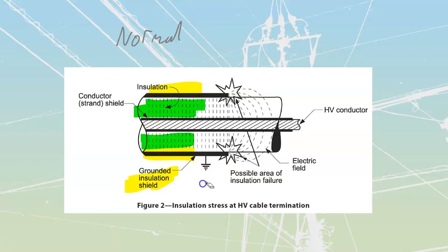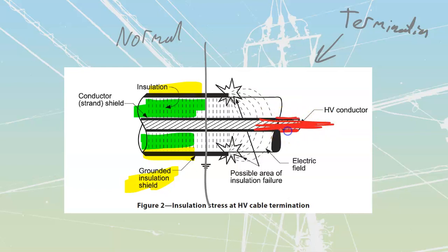When we cross over to this side, this is my termination end. Here, the high voltage conductor is in the very middle, with its strand shield around the outside, acting as an extension that prevents corona, which you'll hear about in section 4.3. By the way, corona on high voltage isn't a virus - it's ionized gas that's highly destructive to components.